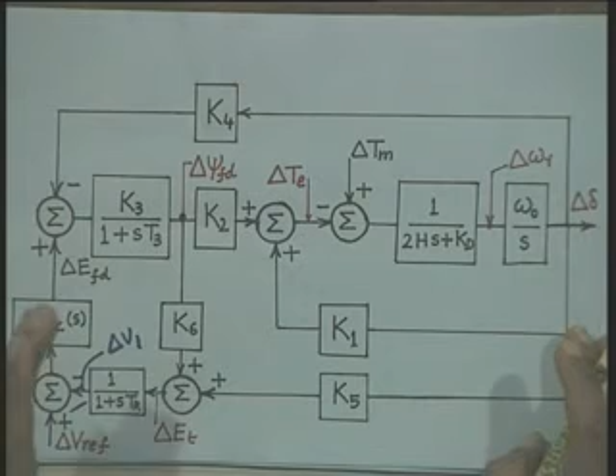Now, to illustrate what is the effect of AVR gain, we take this typical example where the constants of the model are given as K1 equal to 1.591, K2 equal to 1.5, K3 equal to 0.333, K4 equal to 1.8, T3 1.91, K5 is minus 0.12, K6 0.3. The time constant Tr is taken as 0.02, a small time constant. The exciter is represented by a gain Ka. Okay. Inertia constant H of the system is 3 and Kd equal to 0. In fact, these are the parameters of the complete system, right. Although, when we are trying to analyze the synchronizing torque coefficient produced due to delta psi fd or due to the AVR action, right, the H will not be required.